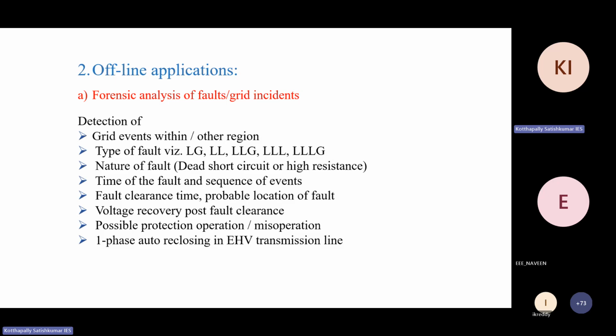Type of fault. Once you have phasor measurement, the PMU already gives you the positive sequence components of voltages and currents. Using those positive sequence voltages and currents, you can tell whether it's an LG fault, LL fault, LLG fault, triple L fault, or triple LG fault. And you can tell the nature of the fault, whether it is a dead short circuit or high resistance. As you know, a dead short circuit means the voltage will be almost zero, whereas in a high resistance fault, the voltage will be there because of the fault resistance.